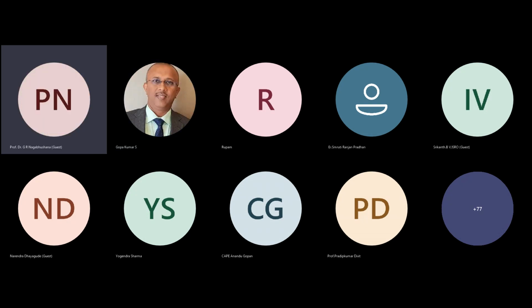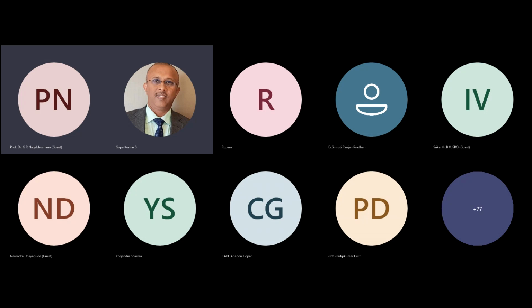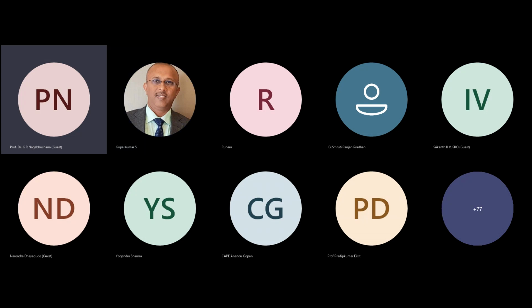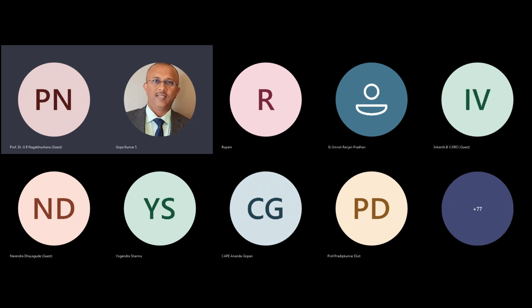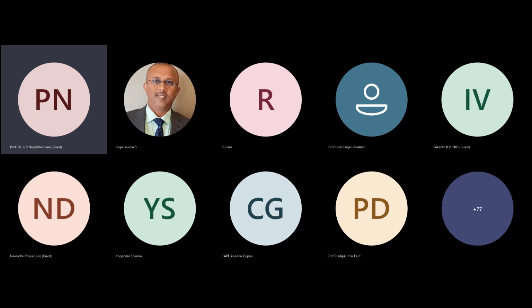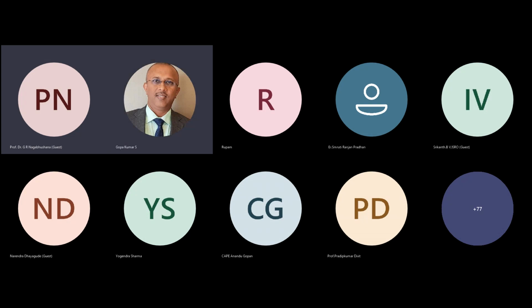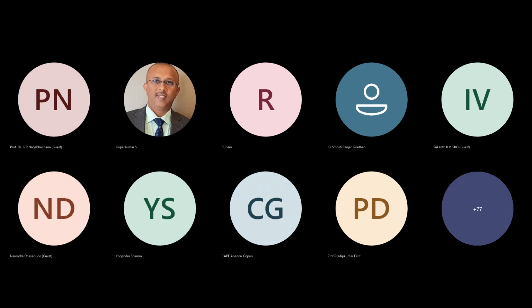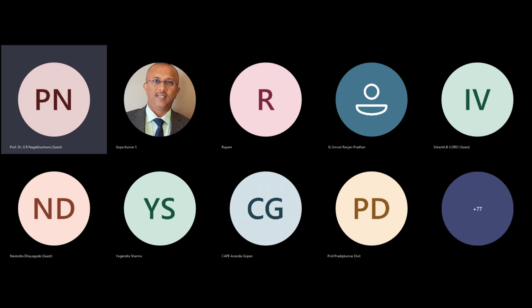There's also a question from Mr. Randir Kumar: we have a 220 kV tower which has a lower level than a nearby 400 kV tower. Some days ago, lightning hit the 220 kV tower and not the 400 kV tower. The answer is the same as before. There are two or three things to consider: where is the step leader coming towards, the taller one or the shorter one? What is the separation between them, several hundred meters? It can be 700 meters easily. If there is a 700 meter difference, the probability is definitely towards the taller object, no doubt about it. But as I told you, if the electric field strength of the air is weaker in the proximity of the shorter object, it will develop towards that one more efficiently. That's the same answer as the earlier question.